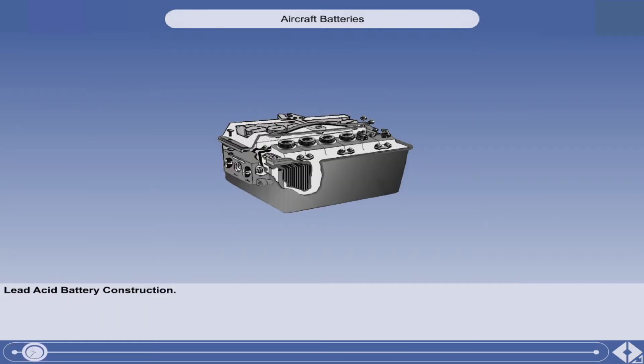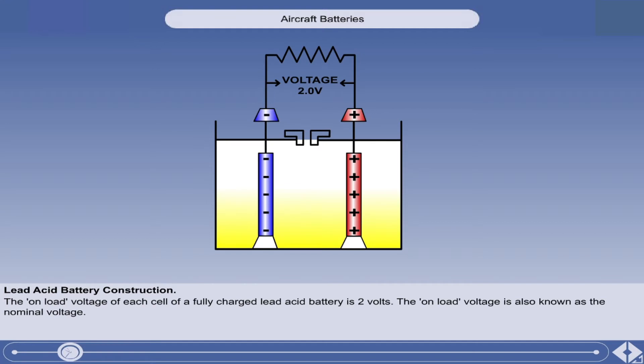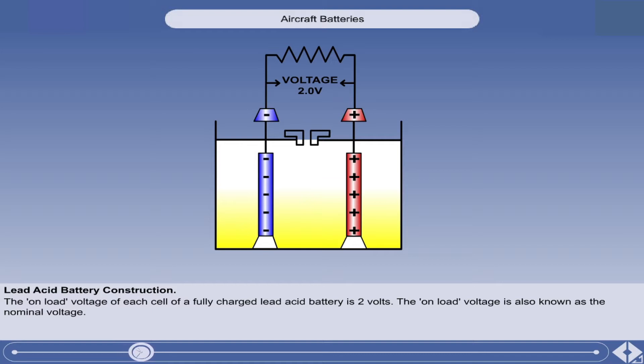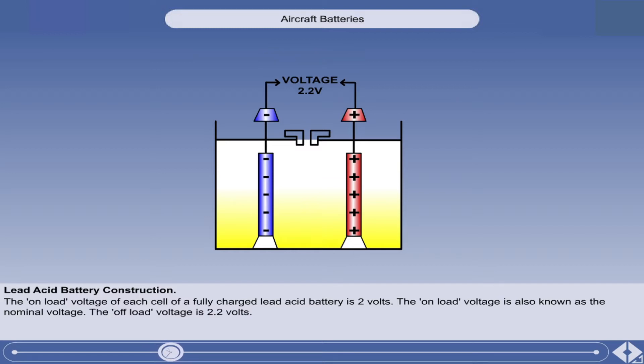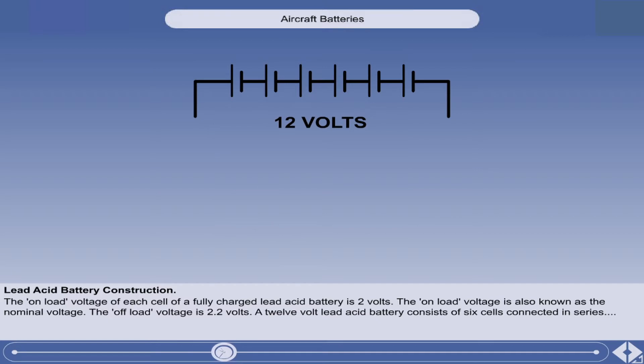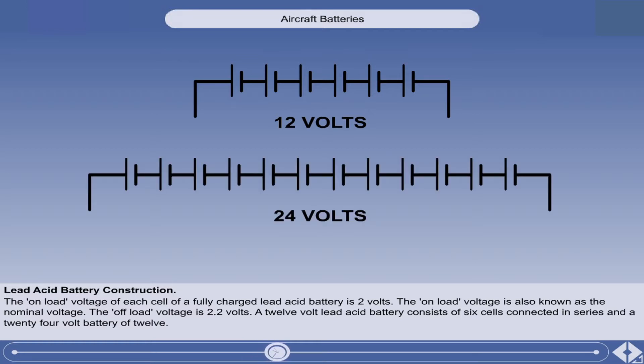One of the most common types of secondary cell battery is the lead acid battery. The on-load voltage, or the voltage with a load being taken, of each cell of a fully charged lead acid battery is two volts. The on-load voltage is also known as the nominal voltage. The off-load voltage, or voltage with no load applied, is 2.2 volts. A 12-volt lead acid battery consists of six cells connected in series, and a 24-volt battery of 12.